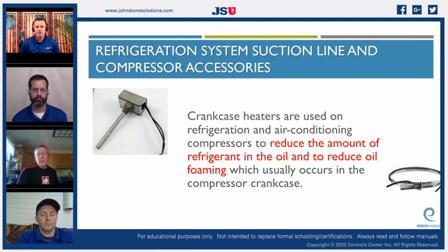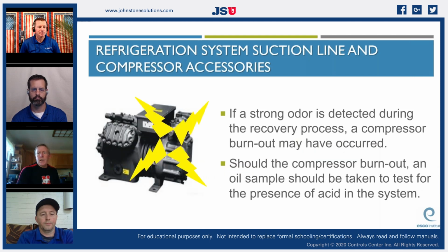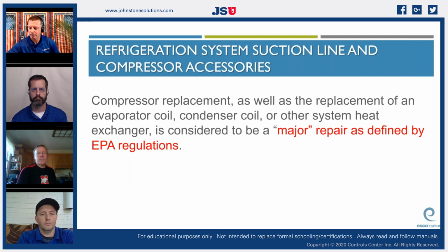Crankcase heaters, we talked about this earlier, reduce the amount of refrigerant in the oil and reduce oil foaming. Almost all heat pumps will have some kind of crankcase heater, either a wrap-around on the right or a submersible in a well on the left. If you have one that goes bad, you can replace it with a wrap-around. Anything to keep the oil warm enough to keep the refrigerant from migrating to it. Again, check for burnouts and check the condition. We used to carry a burnout sampling kit for the residential ones, a quick check to see if we had any burnout.